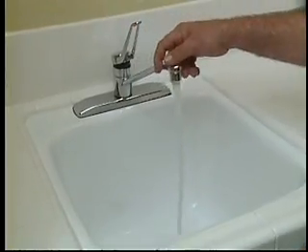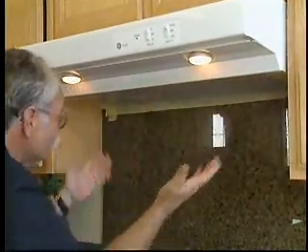When I come out to the house, Steve, I walk around and familiarize myself with the house, and then I start preparing the house for the test itself. Make sure that all the exterior windows are closed, all the exterior doors are closed, all the interior doors are open, because we want to measure every room, the whole house. And I check plumbing traps to make sure they're full of water. And any exhaust fans that have dampers, I make sure that they're closed off, because we want to prep the house for its normal operating conditions.